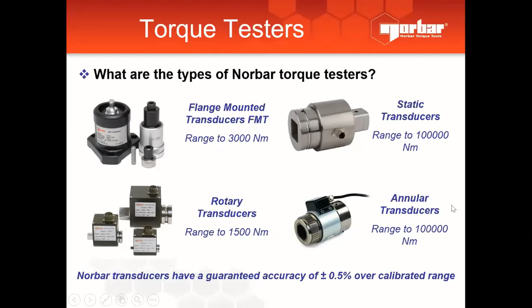Can the torque testers themselves be tested? Yes, the torque tester or transducer themselves can be calibrated. Their calibration goes back to the layman term, the traditional type, using weights and beams. The beam is the distance, the weight is the force, so force times distance equals torque. That's how we calibrate torque.